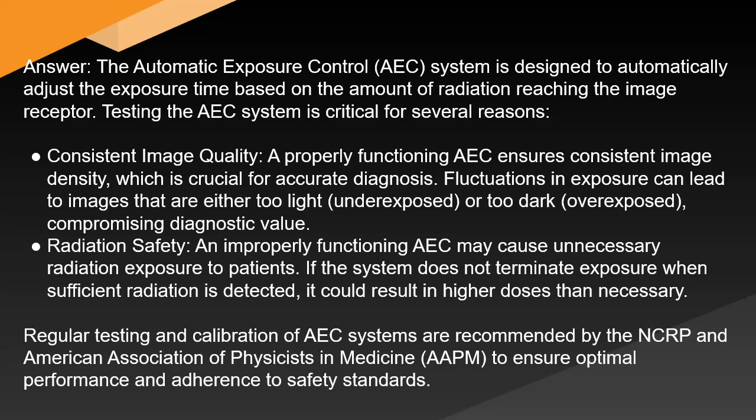Consistent image quality: a properly functioning AEC ensures consistent image density, which is crucial for accurate diagnosis. Fluctuations in exposure can lead to images that are either too light (underexposed) or too dark (overexposed), compromising diagnostic value. Radiation safety: an improperly functioning AEC may cause unnecessary radiation exposure to patients.